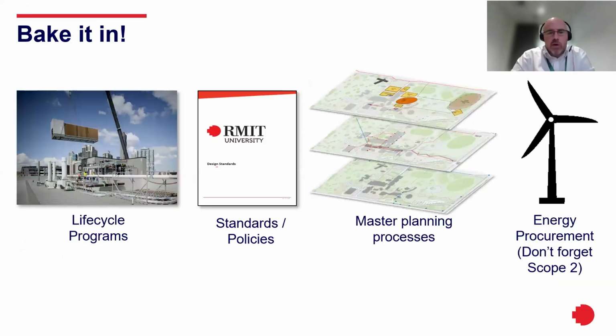Can't forget to bake it in though. I mentioned a program to go through all of the other assets. You need to build that into your portfolio lifecycle program. You need to have policies and standards that set the parameters for your systems. As an example, fan coil units: if you replace any, size them for appropriate temperature today, and then when you do put a heat pump in at a lower temperature, there's no concerns.